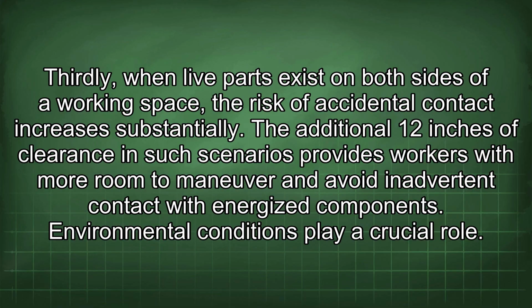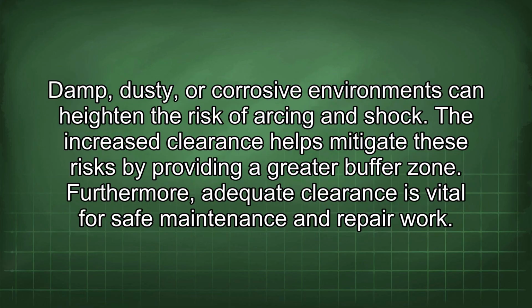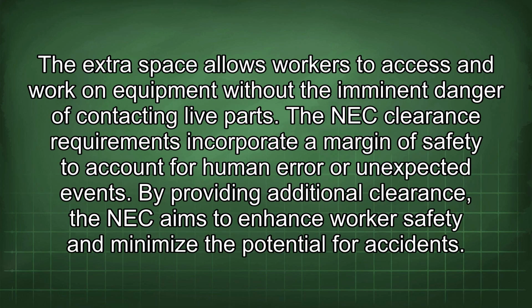Environmental conditions play a crucial role. Damp, dusty, or corrosive environments can heighten the risk of arcing and shock. The increased clearance helps mitigate these risks by providing a greater buffer zone. Furthermore, adequate clearance is vital for safe maintenance and repair work. The extra space allows workers to access and work on equipment without the imminent danger of contacting live parts. The NEC clearance requirements incorporate a margin of safety to account for human error or unexpected events. By providing additional clearance, the NEC aims to enhance worker safety and minimize the potential for accidents.